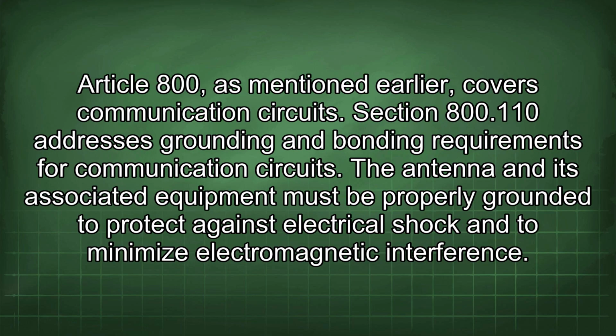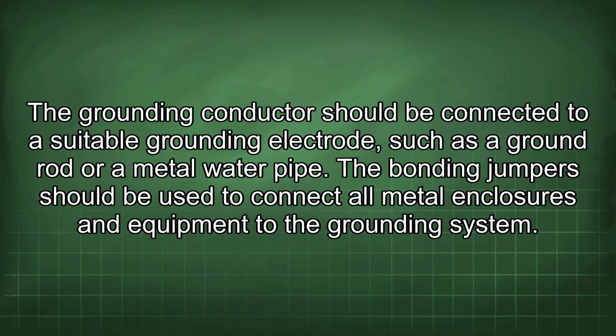Article 800, as mentioned earlier, covers communication circuits. Section 800.110 addresses grounding and bonding requirements for communication circuits. The antenna and its associated equipment must be properly grounded to protect against electrical shock and to minimize electromagnetic interference. The grounding conductor should be connected to a suitable grounding electrode, such as a ground rod or a metal water pipe. The bonding jumper should be used to connect all metal enclosures and equipment to the grounding system.